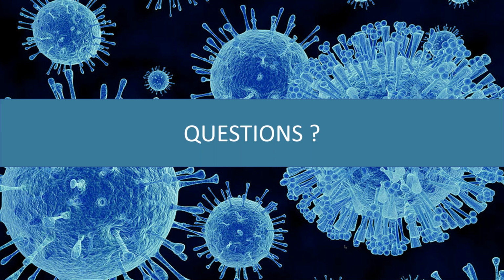There's another question here about, in a crowded office building lobby with screening queues, how should airflow be configured for maximum safety? That's a great question, because that is absolutely a real-world environment that we are going to have to deal with. The traditional mixing ventilation systems, whether an overhead VAV system, fan coils, or even VRF fan coils, unless you're doing an extensive amount of filtration within that space, just mix up all of the dirty air with the clean air. I think you're going to start to see applications like displacement ventilation, where air comes in from a low level, pushes up, stratifies the air, and takes the contaminants in the breathing zone up and away from people. That's going to be a strategy utilized much more in the future.